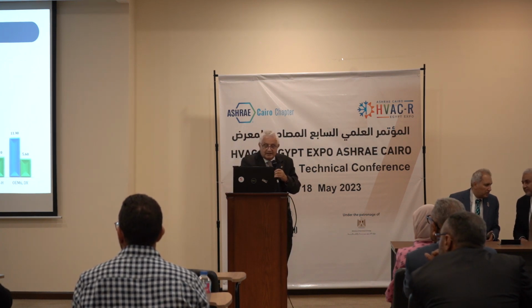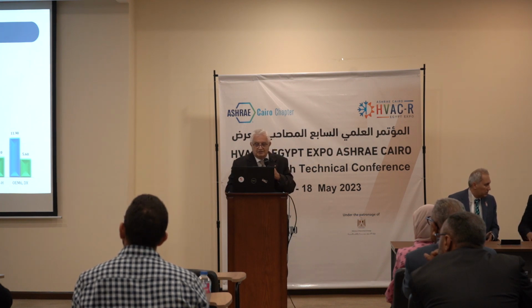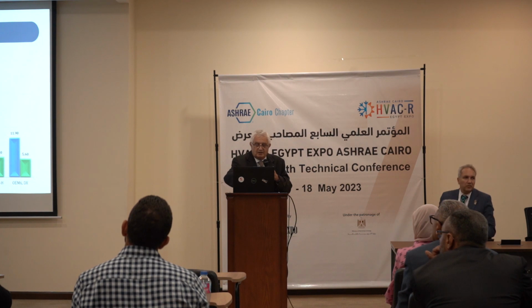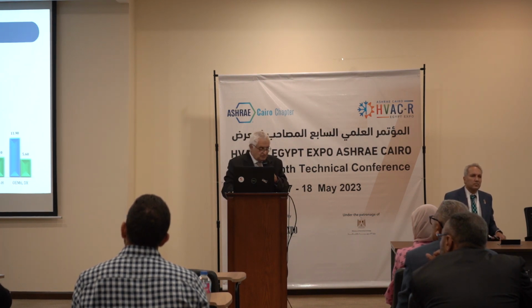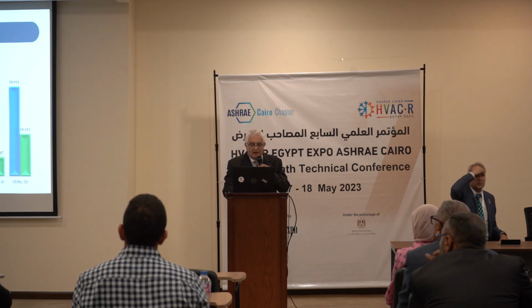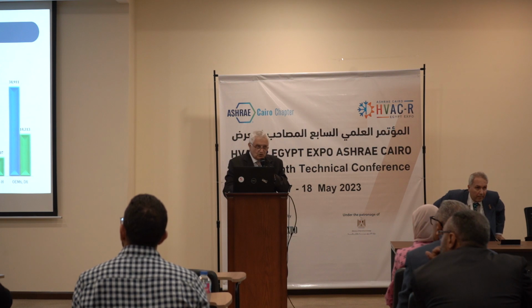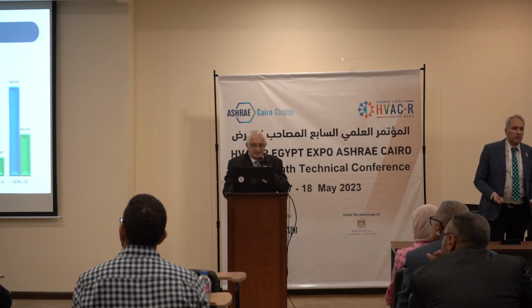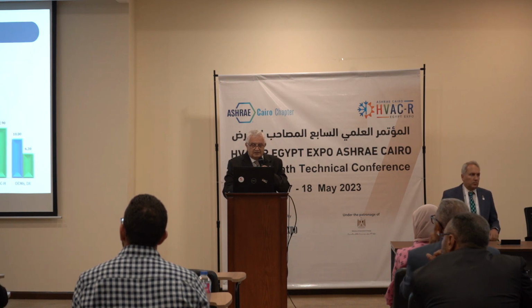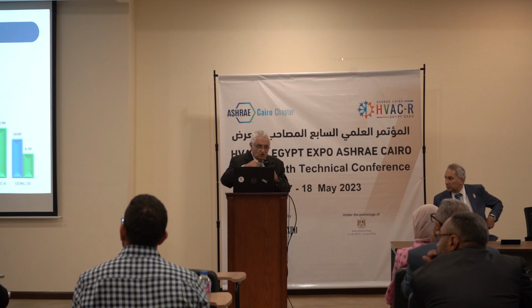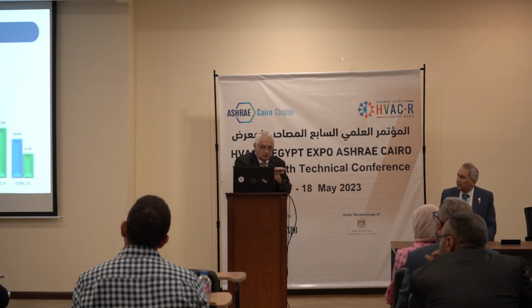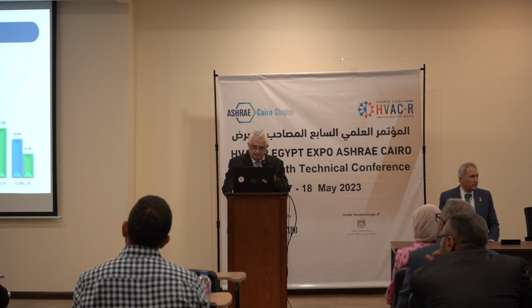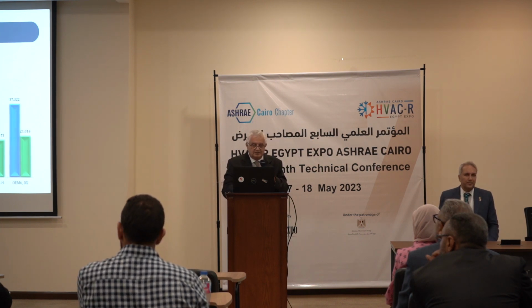Look at OEM3. Again, the EER is higher for the IEC machine for OEM3. OEM4 at climatic zone 2 had a problem with the machine, so we didn't put it inside our graphs. And then the last one, OEM7, we had a higher EER at the climatic zone. So this shows that the EER is higher at the climatic zone for all the units. Now, the capacity is also higher for the IEC machine than the DX machine, yes indeed. And if you look at climatic zone 5, which is the lower humidity zone, again the EER, the blue, is all higher than that of the DX machine. If you look at the capacity, again it's higher.